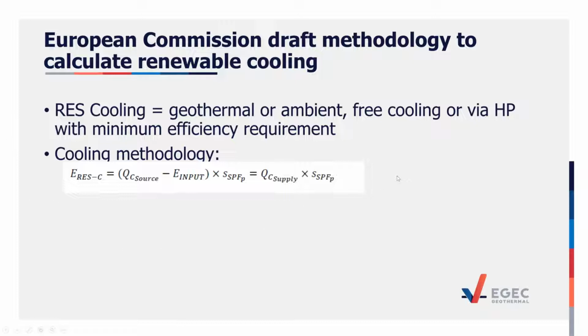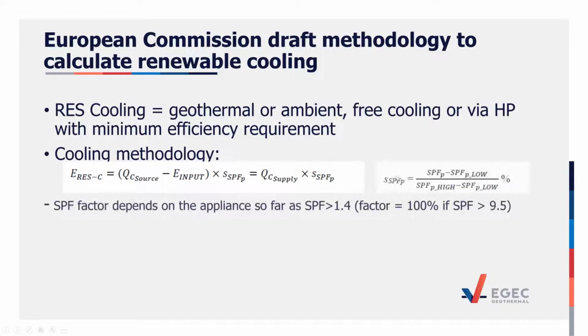How this SPF factor is calculated is very important, and the formula is shown here. This percentage measures the SPF of your individual installation, SPF-P, in comparison with an installation with the highest possible SPF considered by the methodology, which is 9.5. So within the maximum and the minimum, which is 1.4, your appliance, if for instance at 5, would have the given percentage, the given share for this renewable cooling contribution.